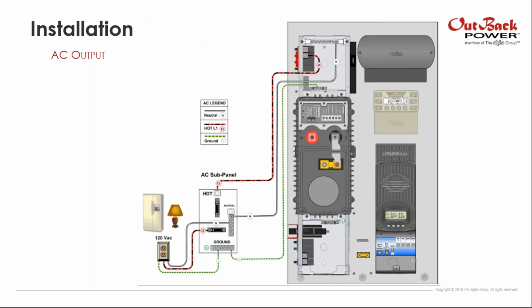Then we will talk about the wiring of the AC output. The AC FLEXware is at the top of the FLEXpower. So at the top we will see a bus bar of neutral. This neutral will come to the bus bar of neutral of your load center, and you will have the breaker of the AC output with the line 1 or the hot to the panel or subpanel terminal in order to power your devices. For the case of ground, it is exactly the same. We will have a grounding bus bar that will be connected to the grounding bus bar of your panel, and that's it.